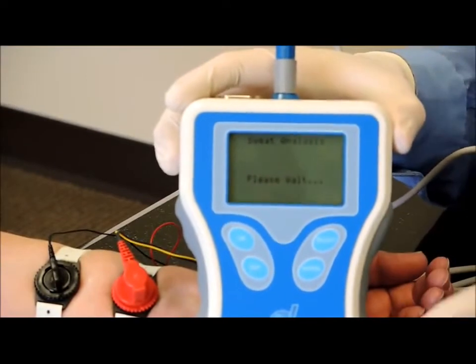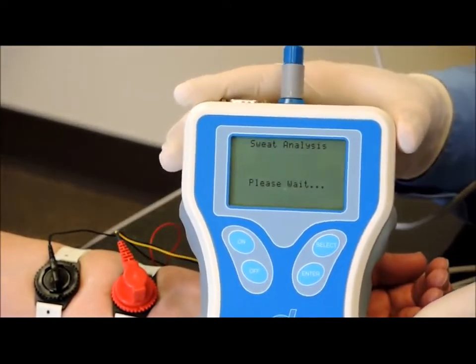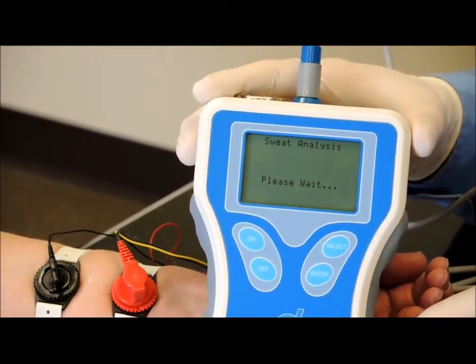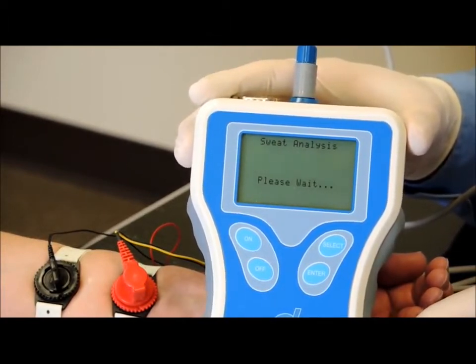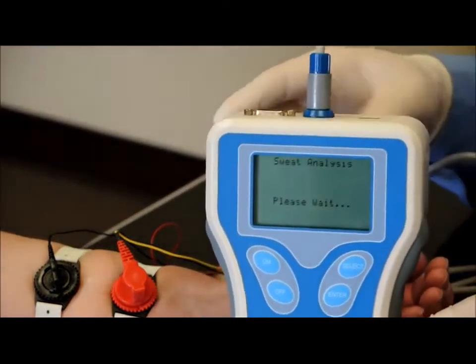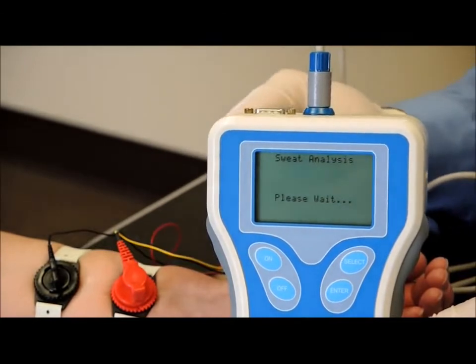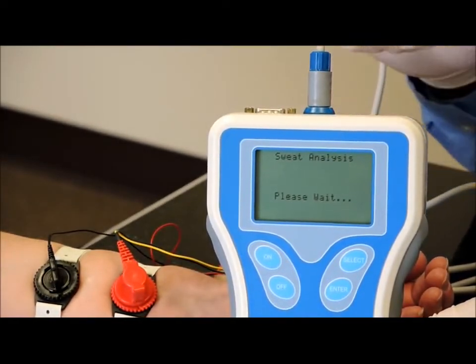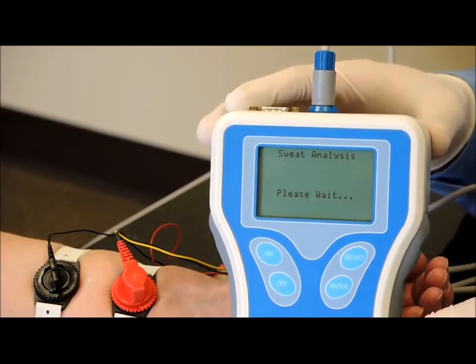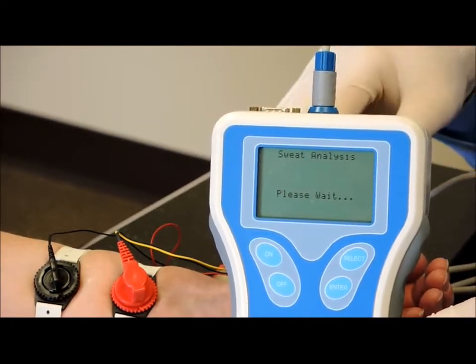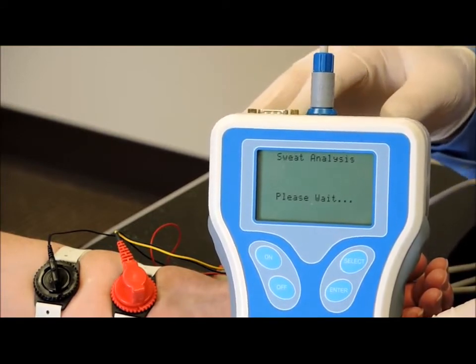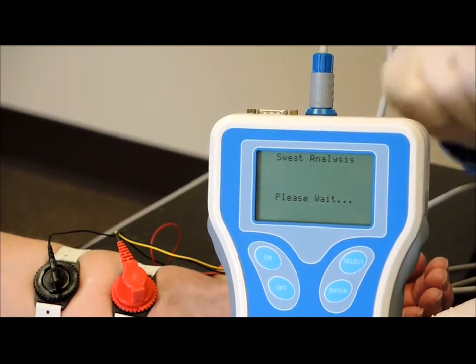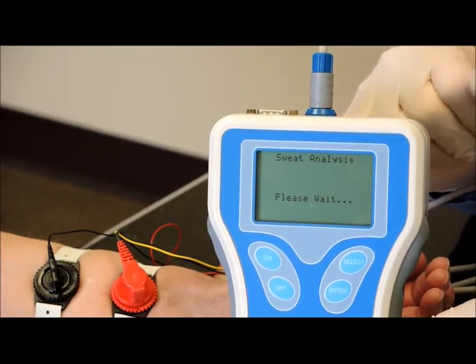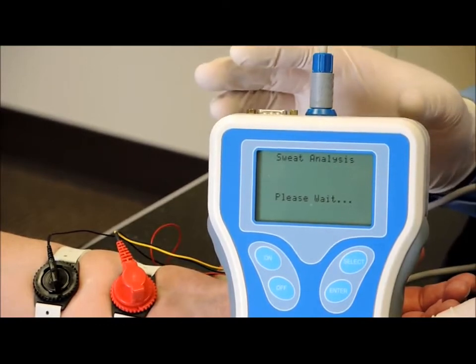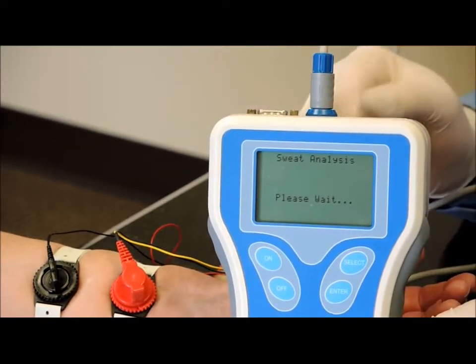So now the Nanoduct says, "Please wait," and we just need to wait. This time can vary depending on how fast of a sweater the patient is. It will stay on this screen until sweat has gone to the first electrode in that sensor cell. And then you'll see the screen say sweat at first electrode. Then as the sweat progresses to the second electrode, once it hits the second electrode, it will start showing values and the sweating rate, and it will take values for 8 minutes.